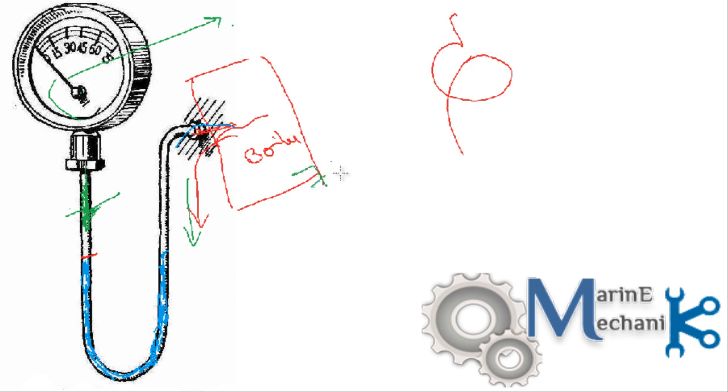So let's say we have a 7 bar boiler and the air over here will get compressed to 7 bar and thus the reading will show 7 over here. So that's how it will be and you might ask a question: will the water get compressed? Of course you know the answer very well, water is incompressible. It just transfers the pressure from steam to air.